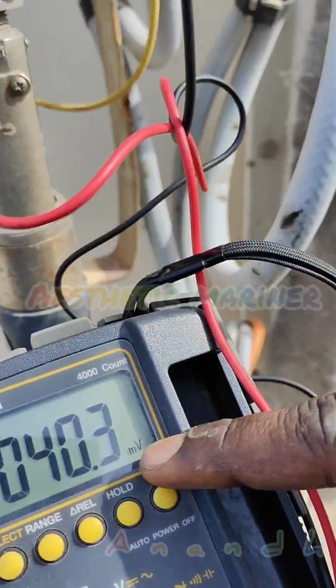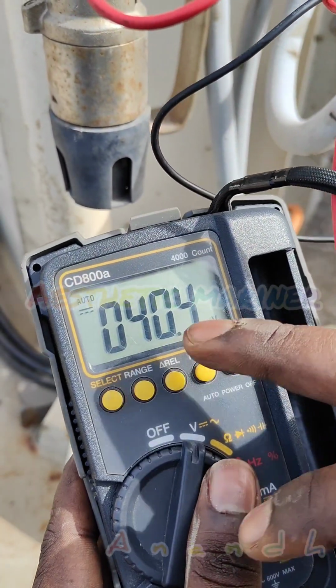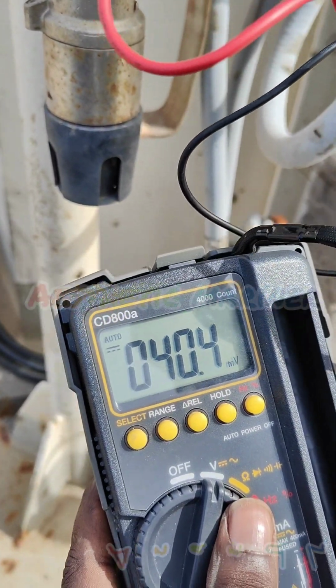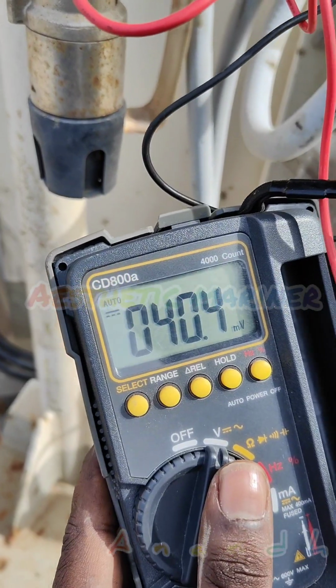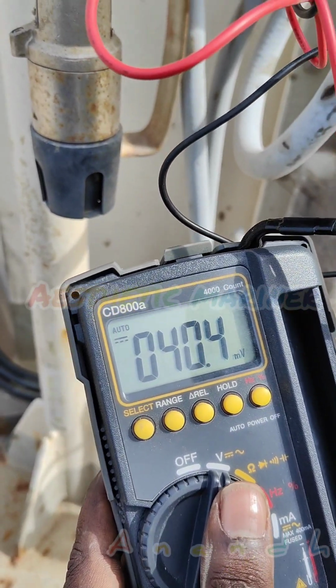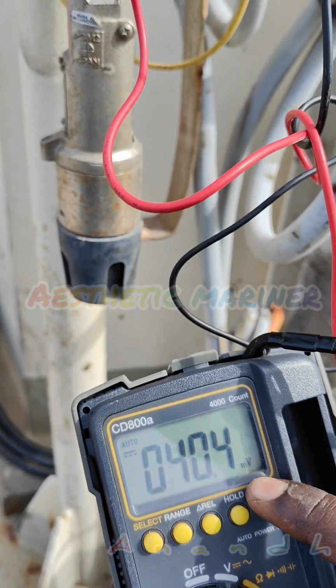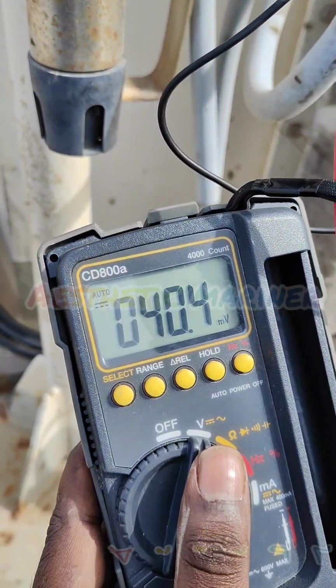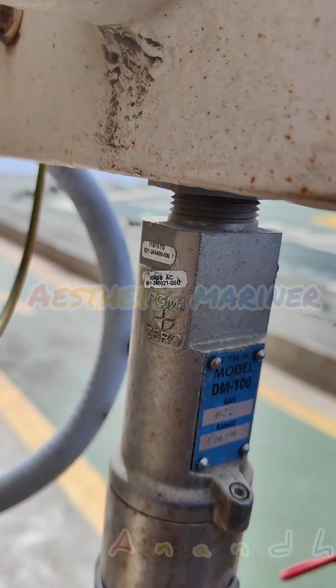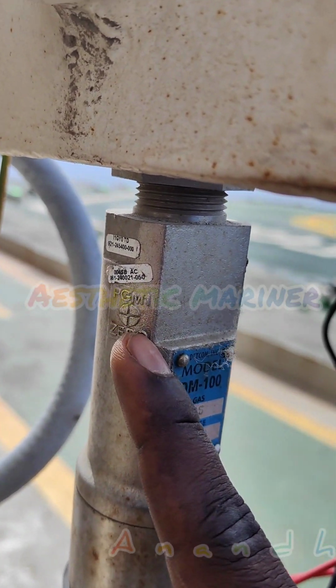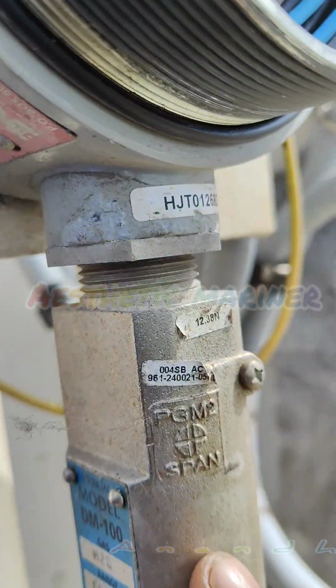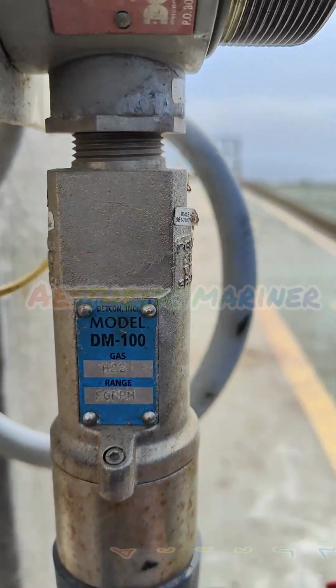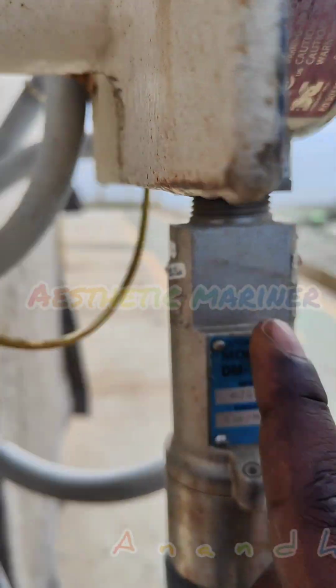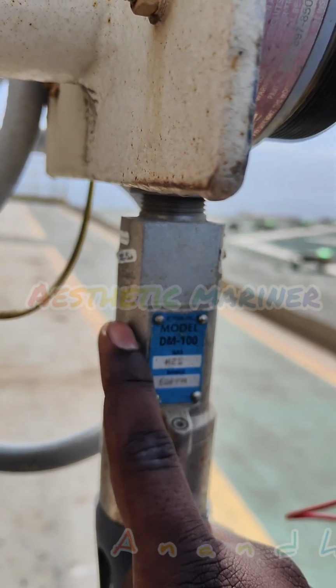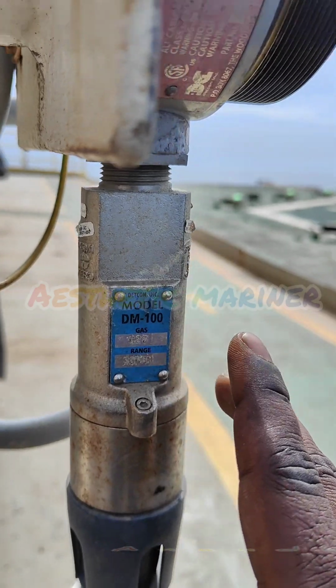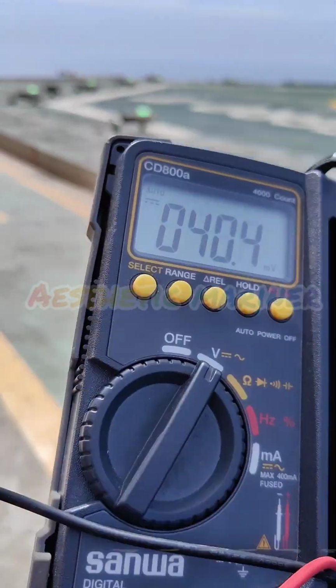Now we have connected the multimeter to the sensor. Here it is showing 40 millivolt. 40 millivolt means 0 ppm, that is 4 milliamps on the 4 to 20 milliamp scale, corresponding to 40 millivolt. For the calibration, we need to know PG1 is for zero calibration and this side, PG2, is for span calibration. For the display type, we hold the magnet on PG1 and wait for the instruction on the display. But in this model, without a display, we follow through the multimeter.